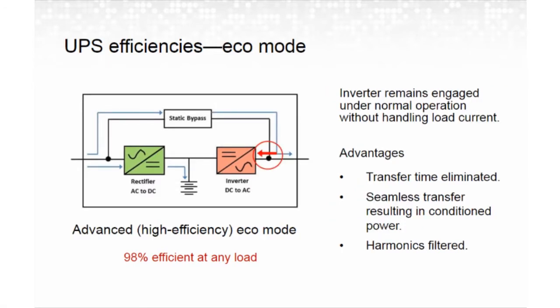Now, to compensate for some of those, you'll see some of the manufacturers are now coming out with what they're calling advanced or high efficiency eco mode. And basically what they're doing is keeping the inverter engaged by backfeeding it. And this allows the load to still be going through the bypass, not the inverter rectifier, but it keeps that inverter energized. And what that helps with is it cuts down on the transfer time. You don't have to wait for the inverter to energize before it transfers. It can be a seamless transfer.